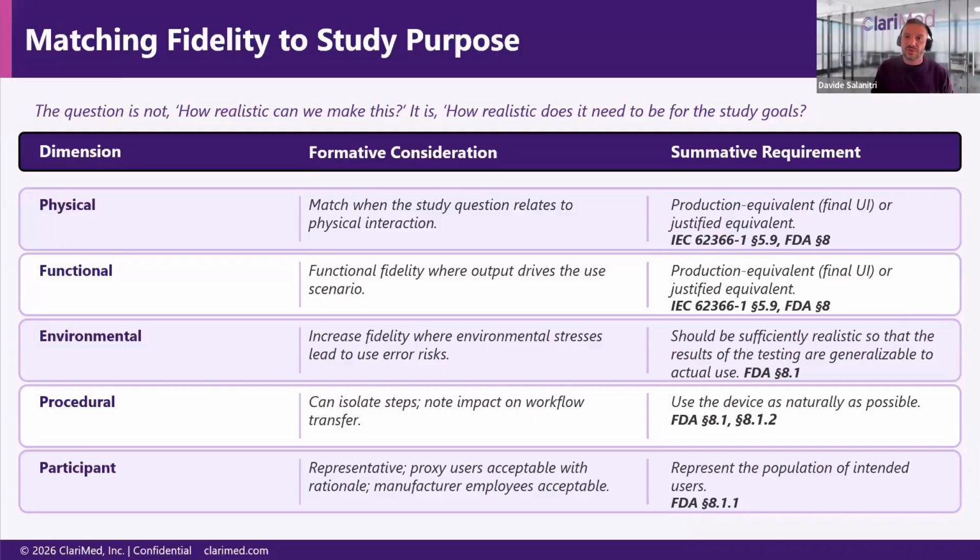Again, if we treat formatives as summative, very few startups can actually afford that, because running a summative for a product is a lot of money for a startup. But what I usually say, and I say it very clearly to some of my clients, especially smaller ones, is: look, formatives allow you to uncover risks, and two types of risks.